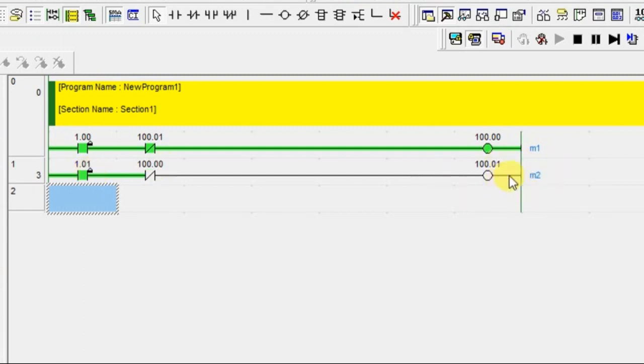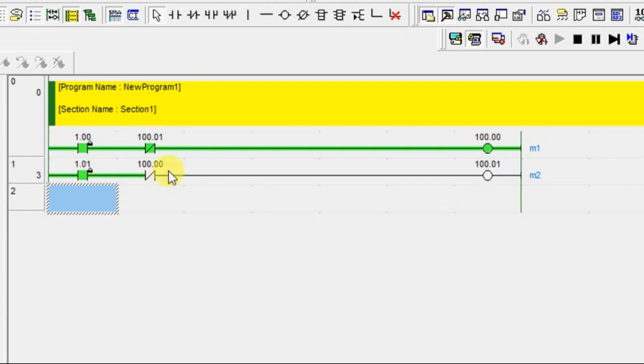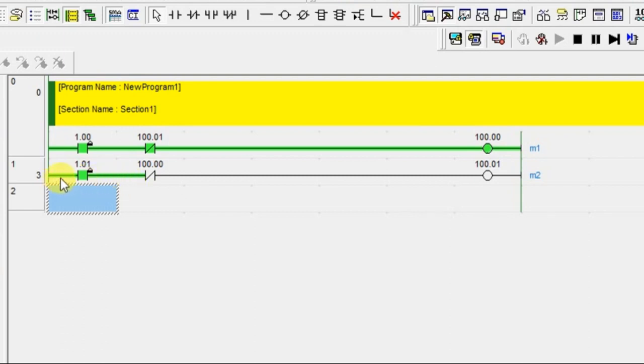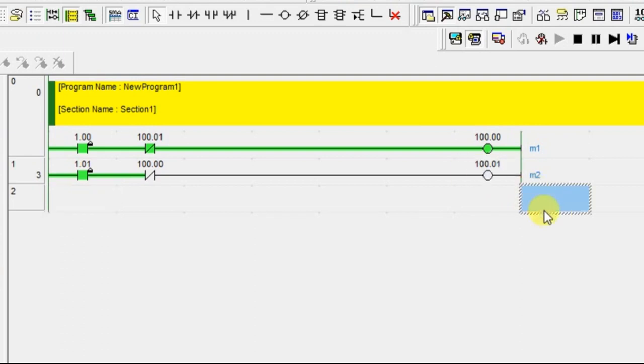Even though they are turning on switch2, it is not turning on M2 because M1 is already in running condition. Since M1 is in running condition, we have used the normally closed contact of M1 here. It is not allowing the power to flow from left to right, so M2 is in off condition.